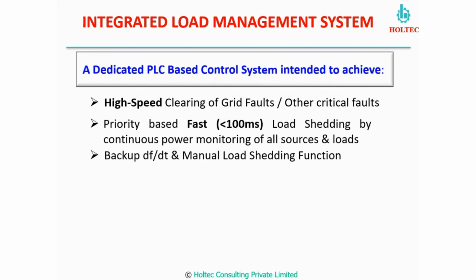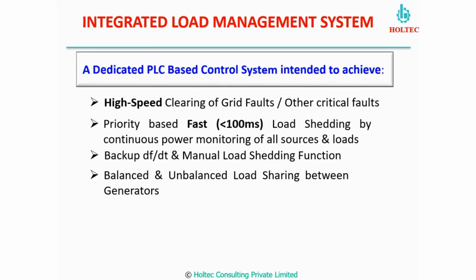Then we also provide backup df by dt and manual load shedding function, which is a backup to this fast high speed load shedding system. Then with that we can have balanced or unbalanced load sharing between generators. We can also control the power received from the grid. We can also control the power factor of the grid. We can also control the power export to the grid.